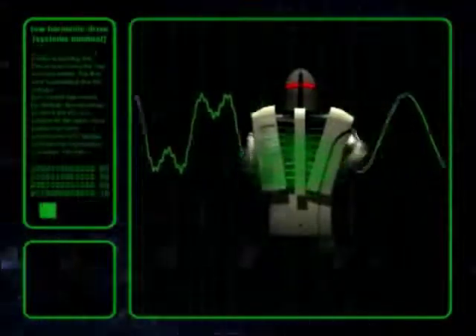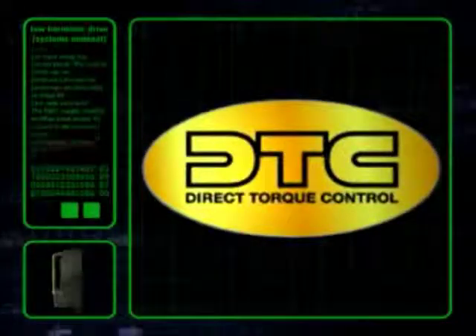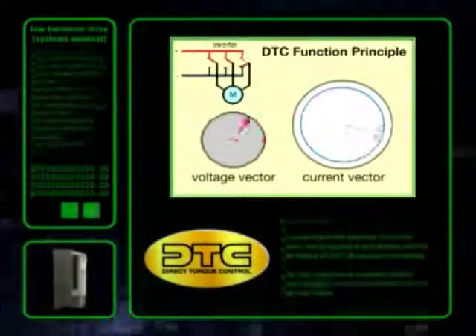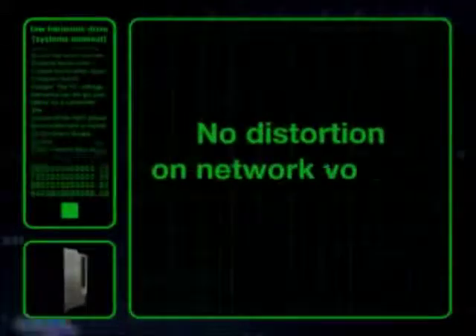So just how does this drive achieve these remarkable feats? The solution uses a switching rate substantially higher than the network frequency, which effectively reduces the low-frequency harmonics. This still leaves some higher frequency noise due to the switching rate, which can be filtered by advanced LCL Low Harmonic Line Filters. This solution does not need additional filtering equipment or complicated multi-phase transformers. The ABB solution uses the principles found in direct torque control, taking the references from the network rather than the motor, creating a sinusoidal wave relatively free of current harmonics, resulting in distortion of less than 5%. This clean sinusoidal current will therefore cause little or no distortion on the network voltage waveform.